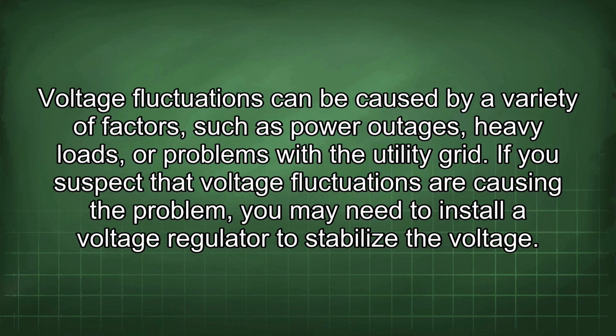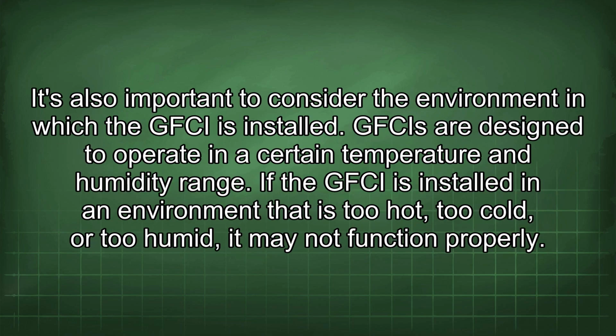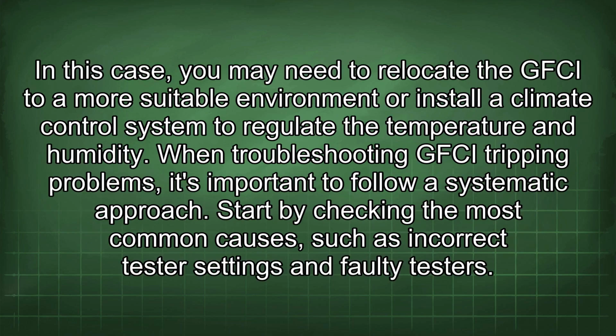to stabilize the voltage. It's also important to consider the environment in which the GFCI is installed. GFCIs are designed to operate in a certain temperature and humidity range. If the GFCI is installed in an environment that is too hot, too cold, or too humid, it may not function properly. In this case, you may need to relocate the GFCI to a more suitable environment or install a climate control system to regulate the temperature and humidity.